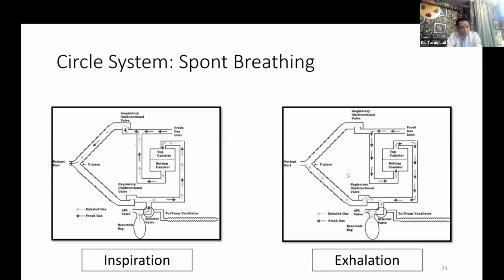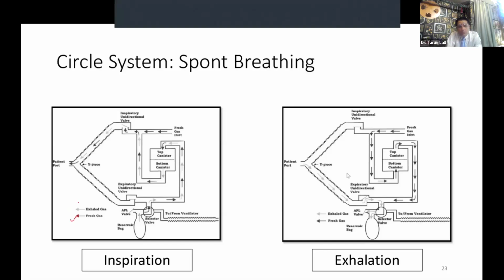Now let us see how this system behaves during spontaneous breathing. It is actually quite intuitive. The fresh gas flow is shown with these dark arrows. The light gray arrows show the exhaled gas. During inspiration, the APL valve remains closed, and whatever gases have collected in the system will just flow towards the patient because of the negative pressure here. Then in exhalation, these gases flow out. Pressure is higher, the APL valve opens, some of the excess gases move out, and the remaining are collected in the bag. Next breath, as the patient creates a negative pressure here, these gases move out. If it is exhaled gas, it then passes through your CO2 absorber. CO2 is absorbed. What is left is clean gas, which mixes with the fresh gas, and then the patient has got gas that is free of carbon dioxide. And that is how the cycle continues.